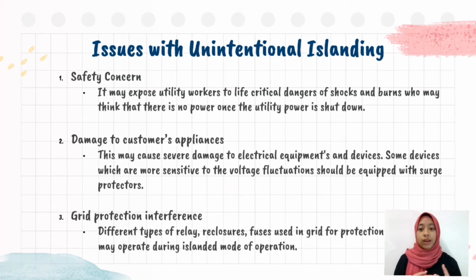Here are the issues when unintentional islanding happens. First, the safety concern. It may expose utility workers to life-critical danger of shocks and burns, since they may think there is no power once the utility power is shut down, but they don't know that the DG is still operating. Second, damage to customer appliances. This may cause severe damage to electrical equipment and devices, because devices that are sensitive to voltage fluctuation should be equipped with protectors. Lastly, grid protection interference. Different types of relays and fuses used in the grid for protection may operate during islanded mode operation.